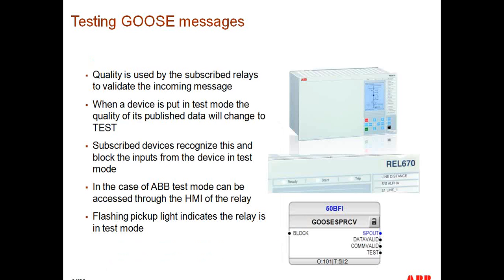So how does this work? Well, quality is used by the subscribed relays to validate the incoming message. When a device is put in test mode, the quality of its published data will change from good to test. Subscribed devices recognize this and block the inputs from the device in test mode. By blocking the inputs from the device in test mode, we mean just that, equivalent to opening up the finger of a test switch. The association is broken and will resume once the quality changes.